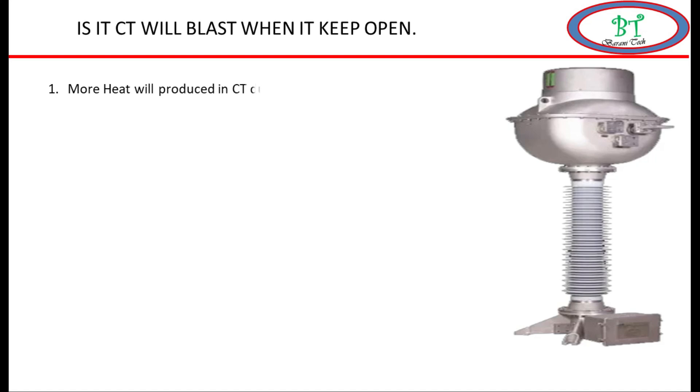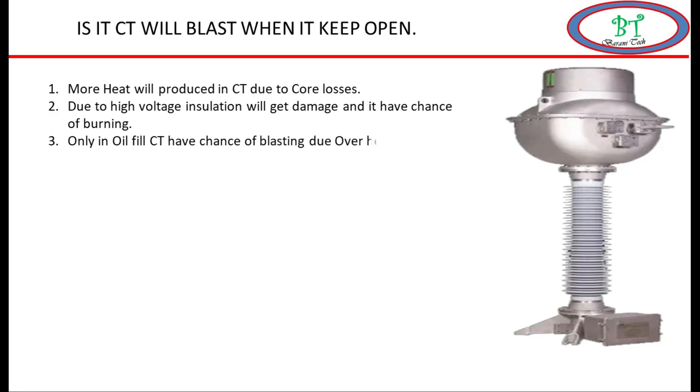Will all types of CT blast when we keep the secondary side open? The answer for this: only oil-type insulated CT will blast due to the following reasons. More heat is produced in CT due to core loss. Due to high voltage, the insulation will get damaged and it has the chance of burning.